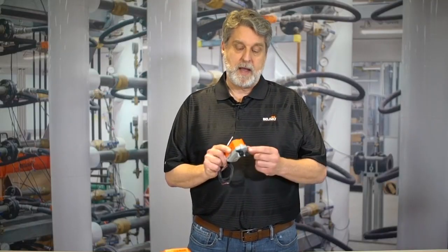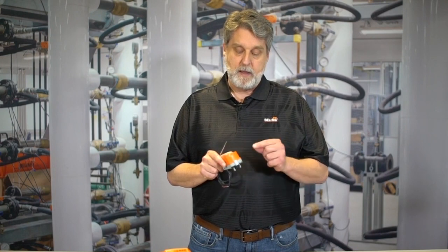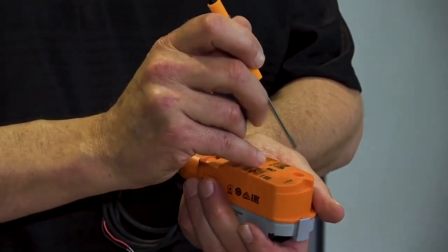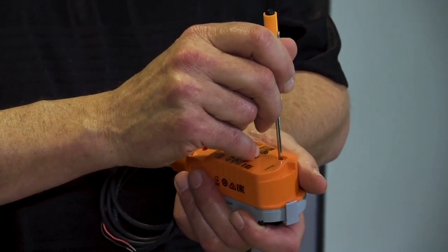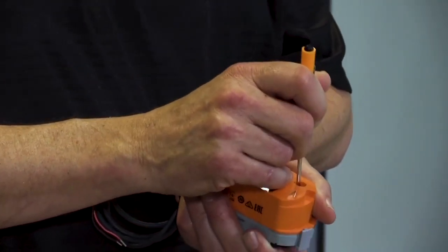Now, I'm ready to go. I've got my clip in the right setting and power to the actuator. Because I've moved the clip and changed what the valve considers full open or full closed, with power to the actuator, I'm going to take something and push down in this hole. There's a small button in there. I'm going to hold it for about three seconds and let it go.